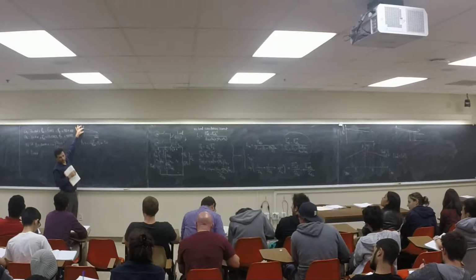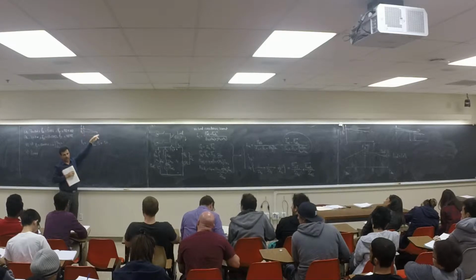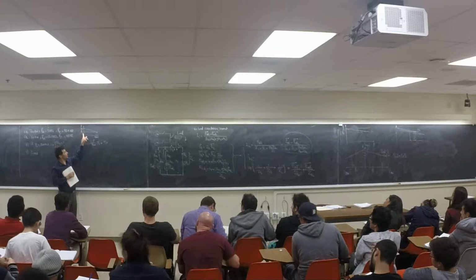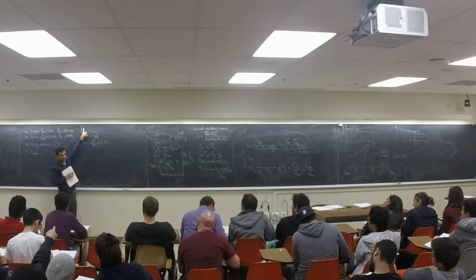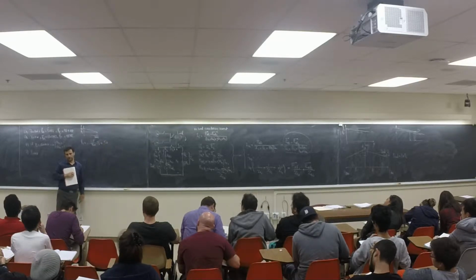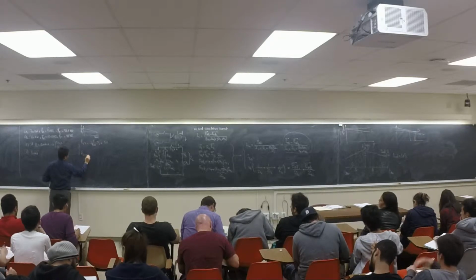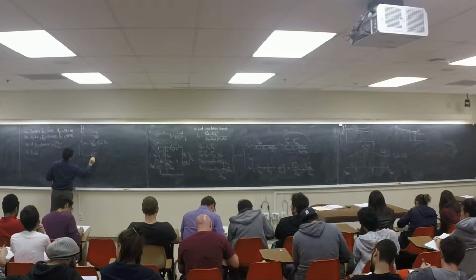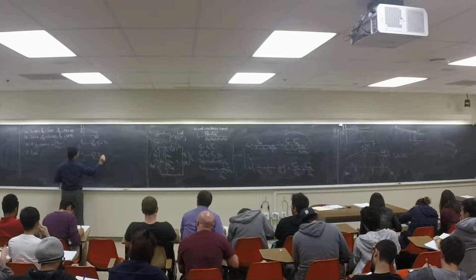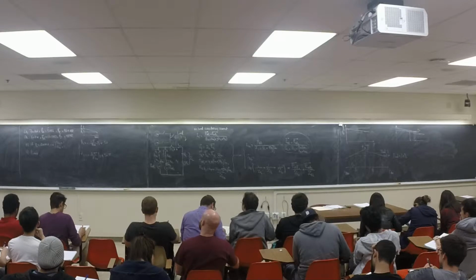So we can say how much is this one? 1.5 divided by 700, right? But the slope is negative, so minus 1.5 over 700 P1. And if P1 is 0, how much is frequency? F_NL, right? So if I put 0 here, this one should be 50. So F1 will be 50. How about F2? Minus 2.5, right? Over 700 P2 plus how much? 50.5, right?